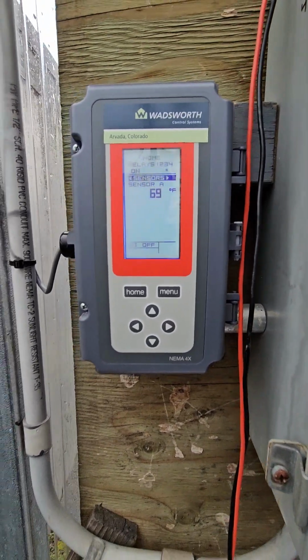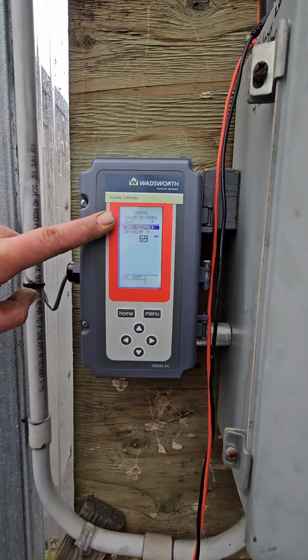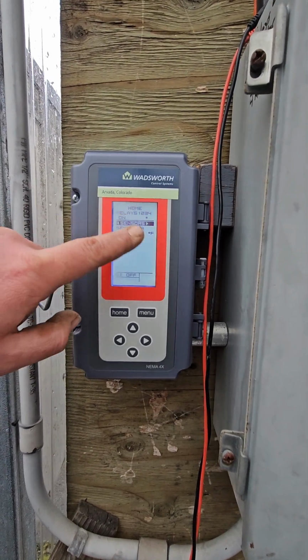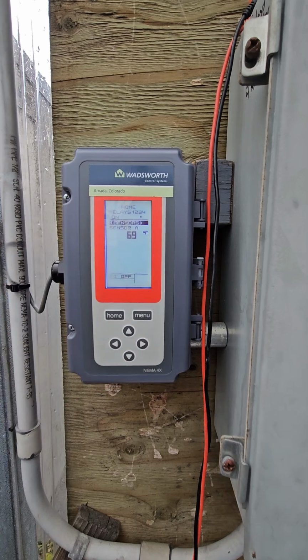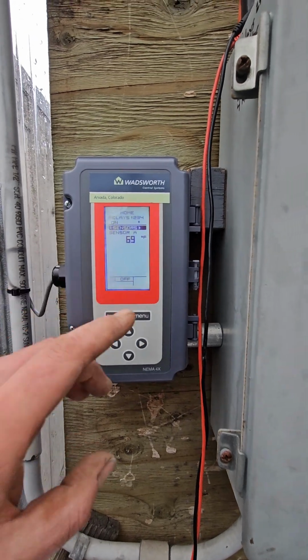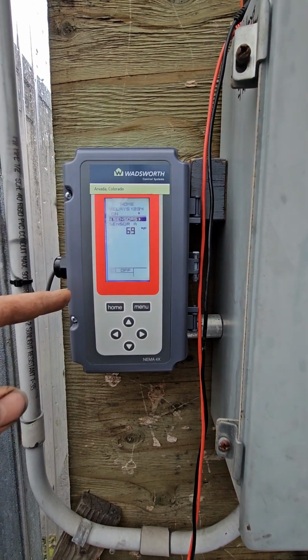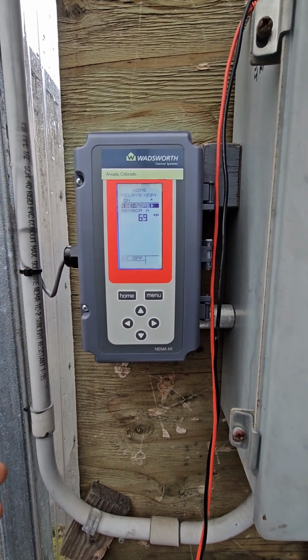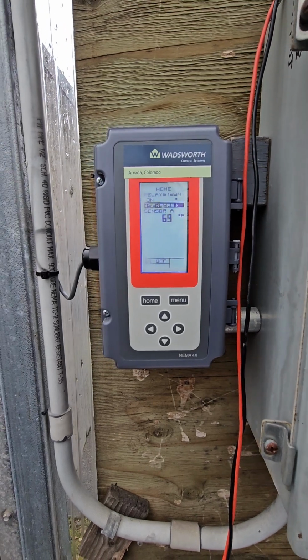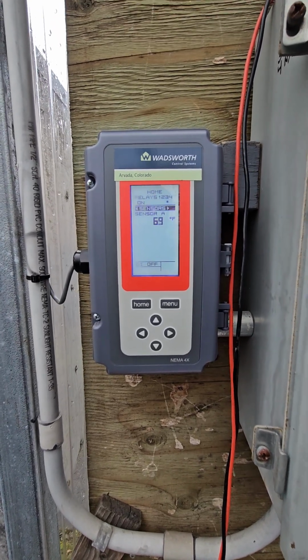So when you set one of these up, you go in and basically tell the relays what function that relay does, is it related to heating or cooling? Depending on how you wire those, there's some time delays in here so that the fan basically waits to turn on until the shutters are open, that sort of thing. So pretty simple relay logic.